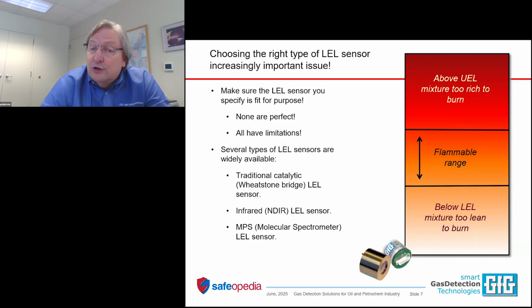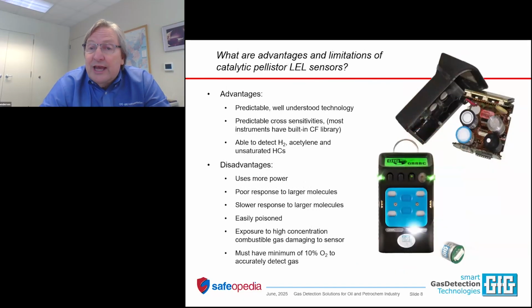Infrared LEL sensors are lower power. They have the advantage of being a better sensor for very large molecules, which are often the majority of the molecules that you're trying to measure if you're measuring crude oil or diesel or jet fuel. And you have another type of sensor called molecular property spectrometer sensors, or MPS sensors, where they're looking at the density of the atmosphere. In fresh air, the density is going to be higher than if you are in the presence of lighter than air combustible gas, or the density will be heavier than fresh air if you're in the presence of heavier than air gases.